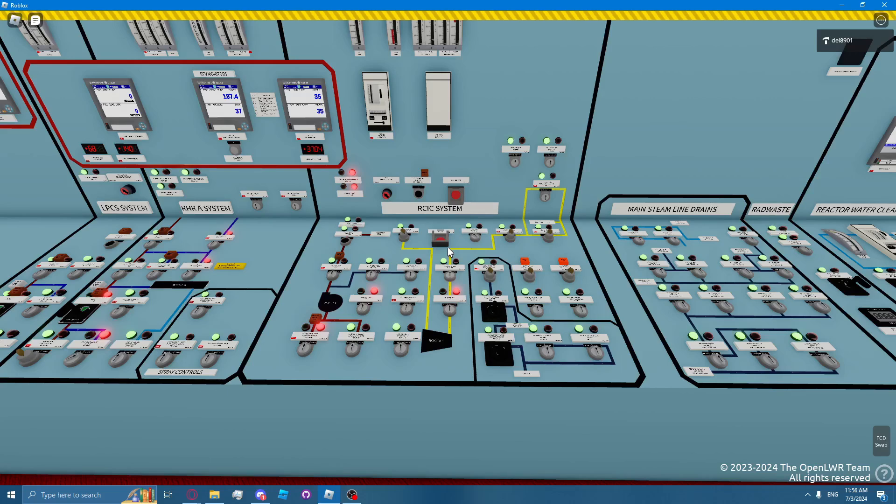The RCIC system can also automatically isolate. Automatic isolation is accomplished through a series of sensors in the RCIC system and RCIC rooms.